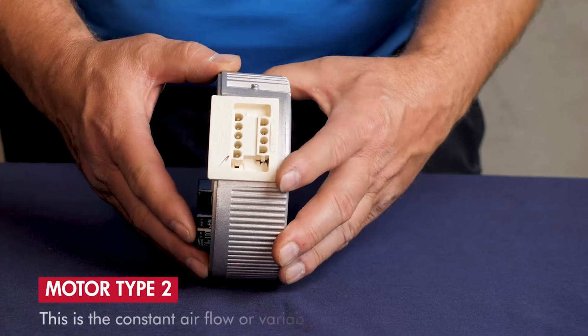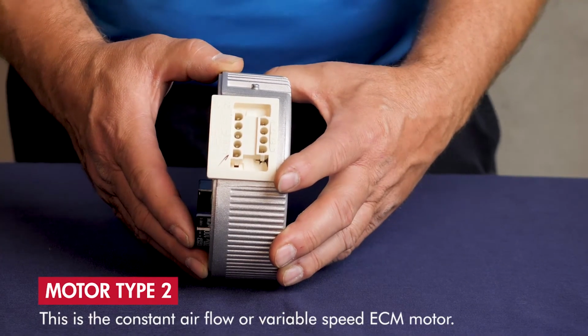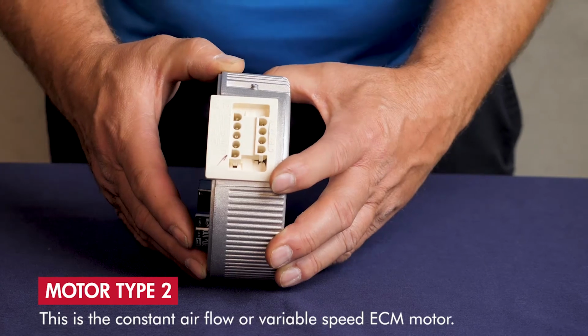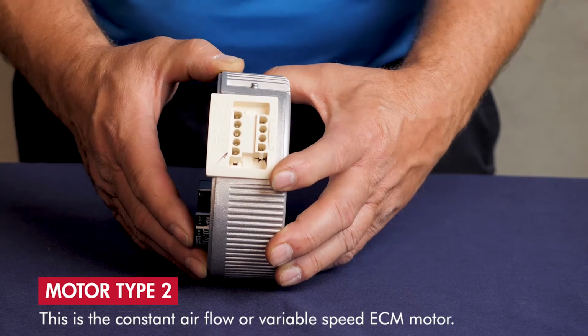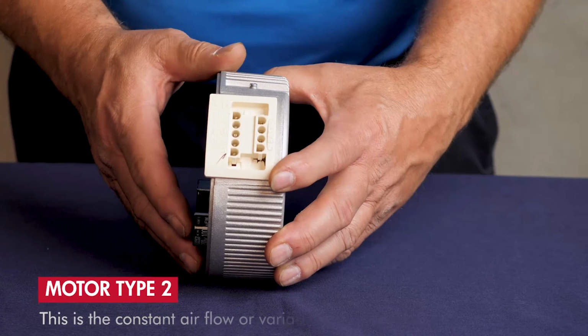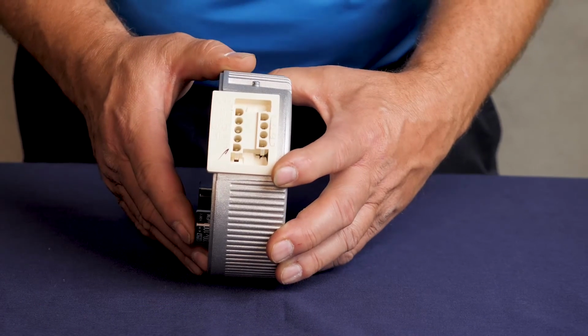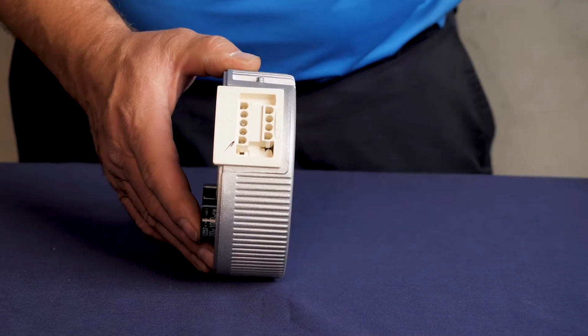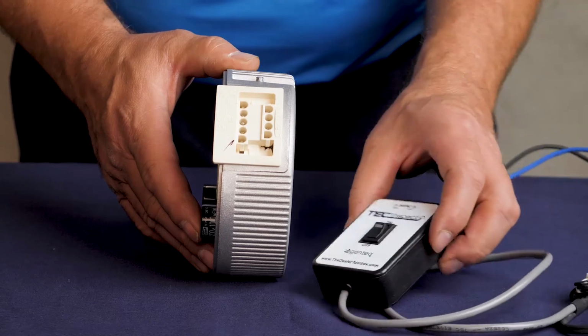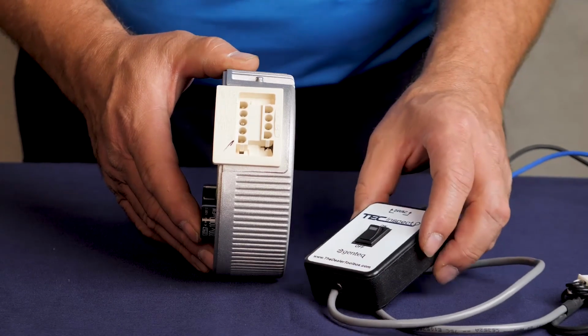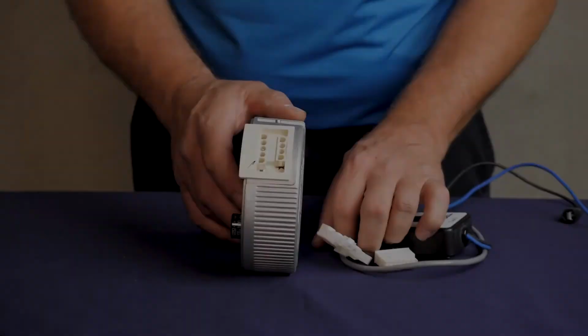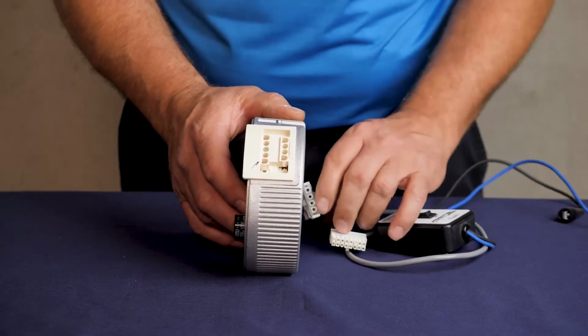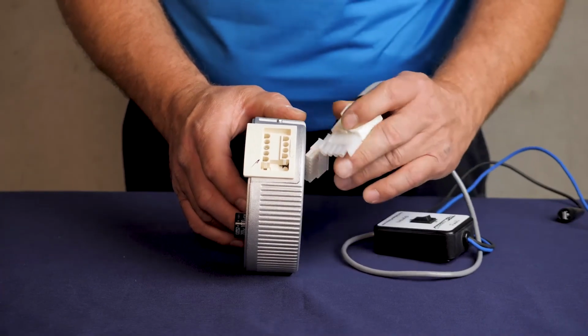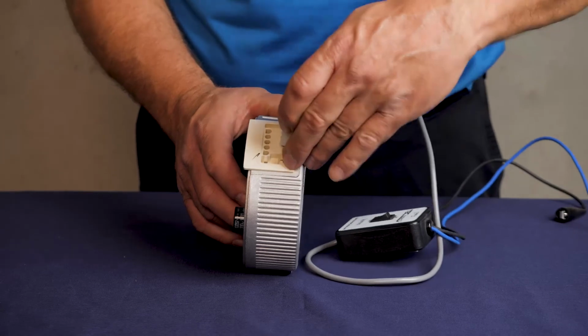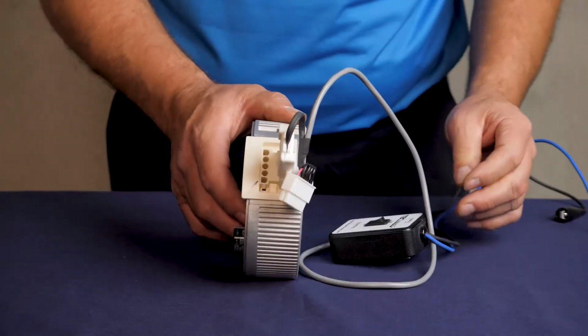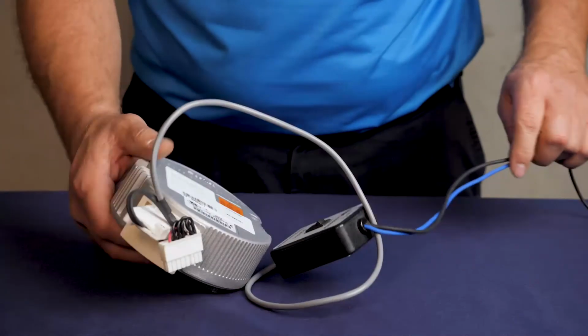This is the module from the Genteq 3.0 variable speed or constant airflow ECM motor. To test the constant airflow motor, it's best to use the manufacturer's recommended tester. This is the TEC Inspect made by Genteq, the motor manufacturer. For this model, the 3.0 motor, we will use the 4-pin connector and plug right in.